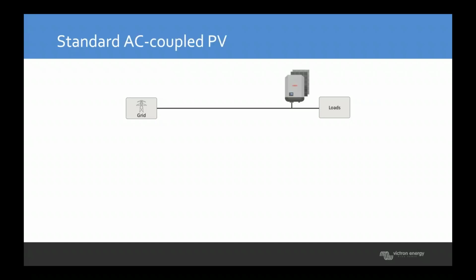Often what will happen is the AC PV will come in first, at least in the Australian market. This is the most cost-effective way to begin a system - you want to save money on daytime power consumption, so you'll add a Fronius AC PV inverter and panels. But the issue with a system like this is if the grid goes down, the system goes down as well, and you lose power even though you have power production on the roof.